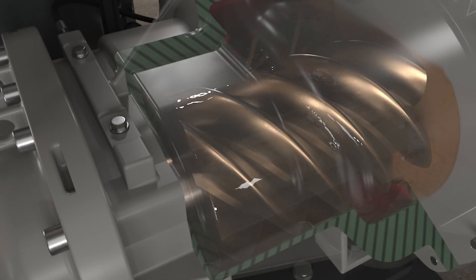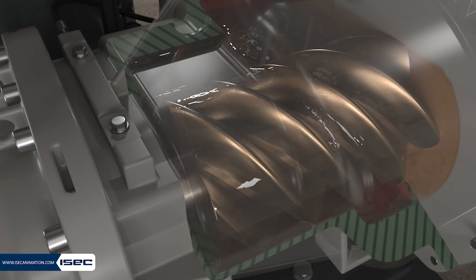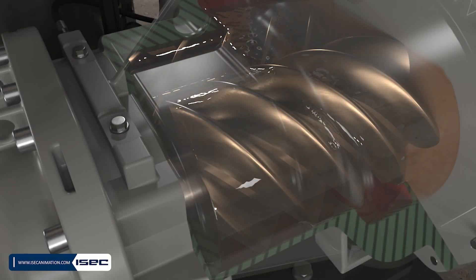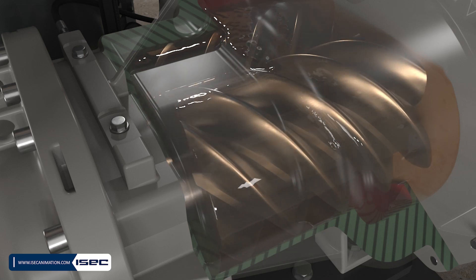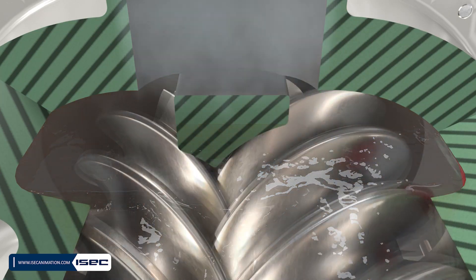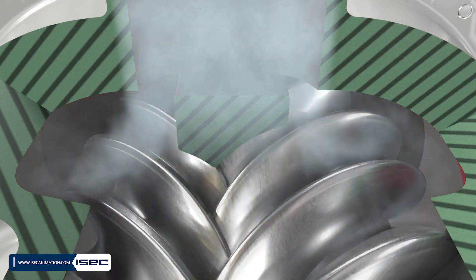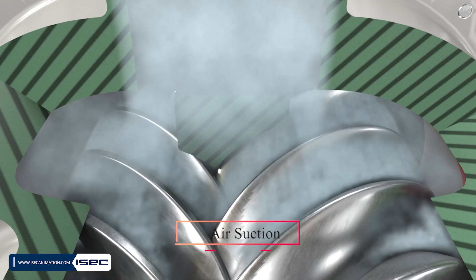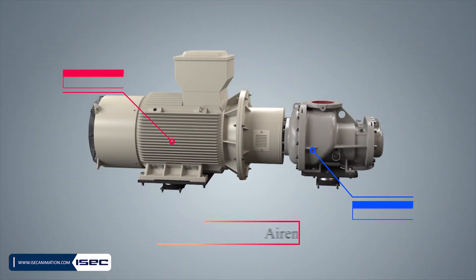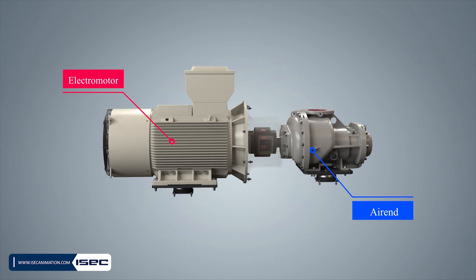Air End. The main task of the air compressor is handled by the air end. Air ends have a specific air flow and oil flow rate, which depend on the dimensions of the chamber and helical rotors. The energy required to produce torque and rotate the rotors is provided by the motor.